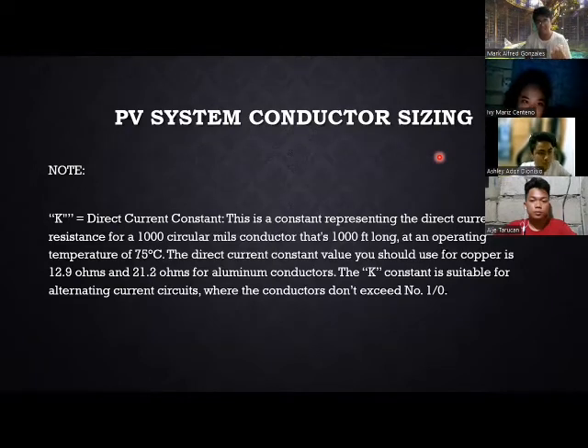Now, K is the direct current constant, or the constant representing the direct current resistance for a 1,000 circular mil conductor that is 1,000 feet long at an operating temperature of 75 degrees Celsius. The direct current constant value you should use for copper is 12.9 ohms and 21.2 ohms for aluminum conductors. The K constant is suitable for alternating current circuits where the conductors don't exceed number 1/0.